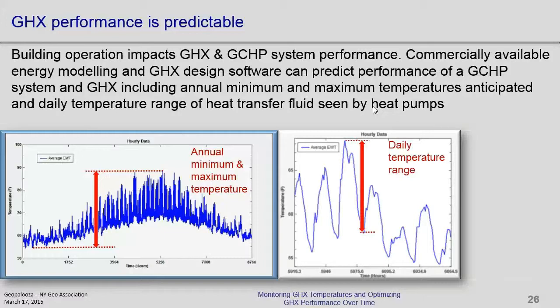Let's say you've got it set back to 60 degrees at night, and you hit it in the morning, and all of a sudden you've got a huge heating load that's spiking up, and somehow you got to extract that energy from the ground. That ground loop temperature is going to go down like crazy. And in order to compensate for that, you've got that peak. If you built that night setback into TRACE, for example, it's going to show up in there, and you'll see that huge spike at 8 o'clock in the morning or 7 o'clock in the morning. And that's what's going to drive the size of that ground loop.